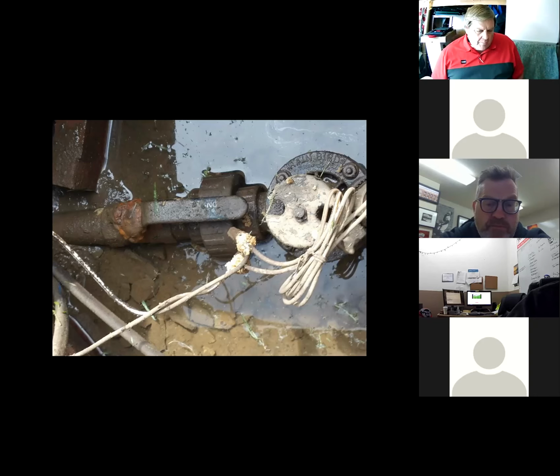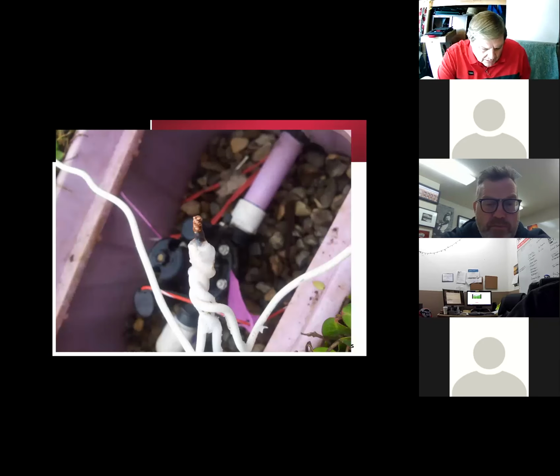So by all means, a waterproof wire connection is the key to setting the system up. Look at this. There's so much corrosion. It's turning black in it. And if you've got the wire pre-twisted so much that your pliers leave marks on the copper, you're going to break the copper wire inside there. Don't pre-twist it. If you have to twist it to get it together, don't twist it tightly, because the wire nut will continue to twist it when you put the wire nut on it. So we have to be careful.